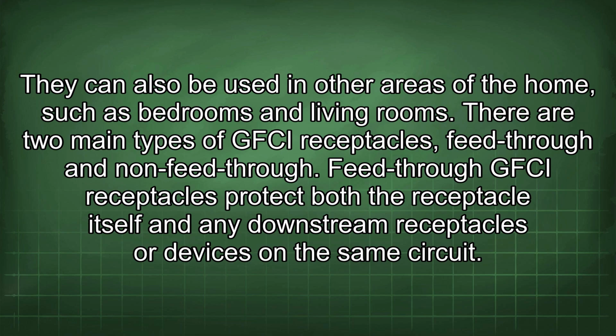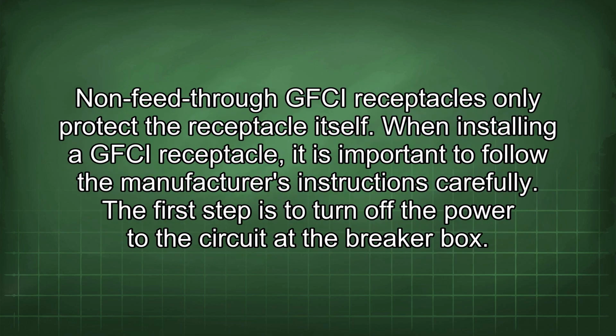There are two main types of GFCI receptacles: feed-through and non-feed-through. Feed-through GFCI receptacles protect both the receptacle itself and any downstream receptacles or devices on the same circuit. Non-feed-through GFCI receptacles only protect the receptacle itself. When installing a GFCI receptacle, it is important to follow the manufacturer's instructions carefully.